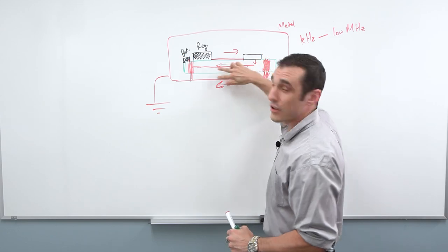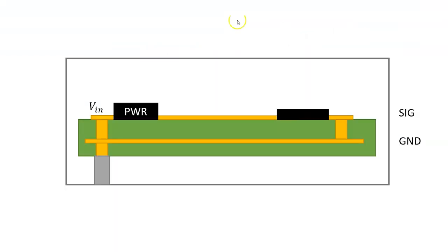This can create a path for high frequency noise traveling along the ground plane and traveling along the enclosure. And so here I have what's called common mode noise. So I want to take a quick detour and show you what I mean when I say common mode noise can happen in this type of system when you have capacitive coupling. So here in this type of diagram that you'll typically see on the guides about common mode noise, there will be some capacitive coupling here in between our ground and our grounded enclosure.